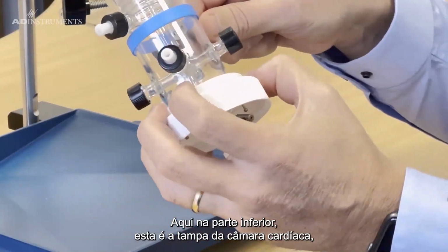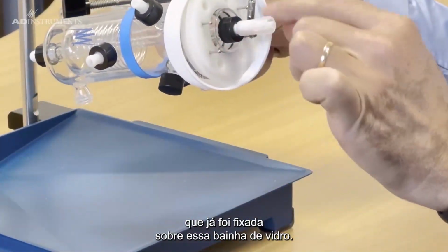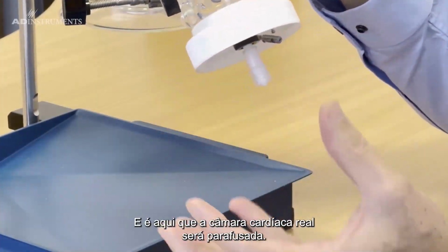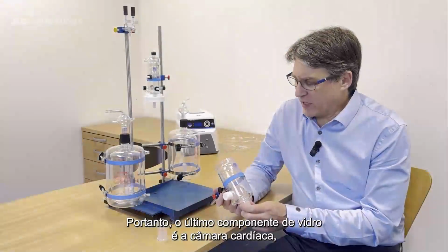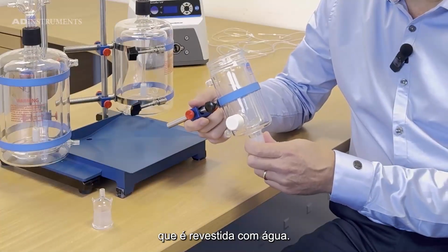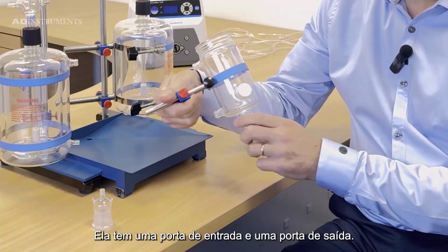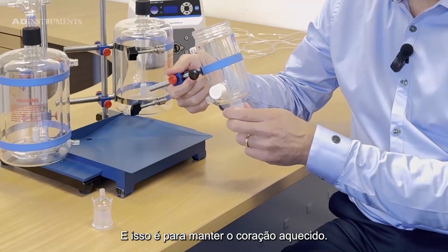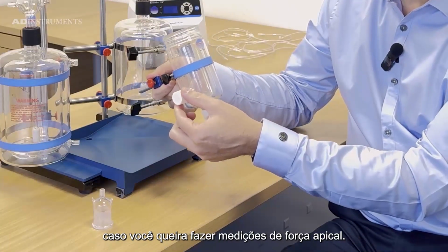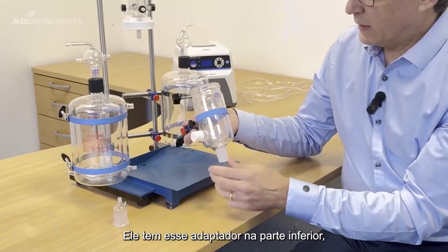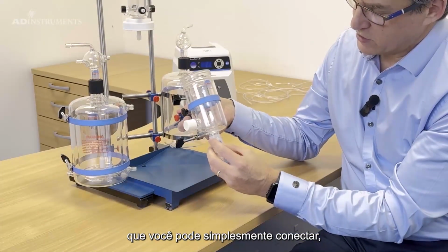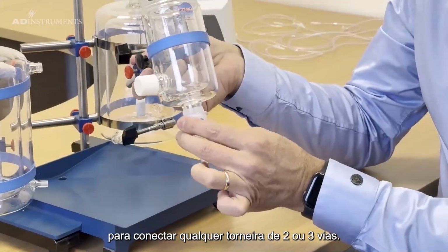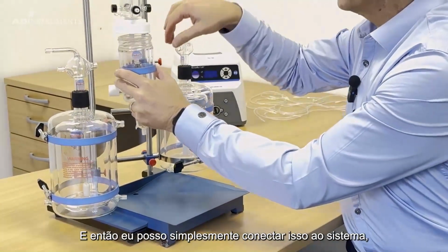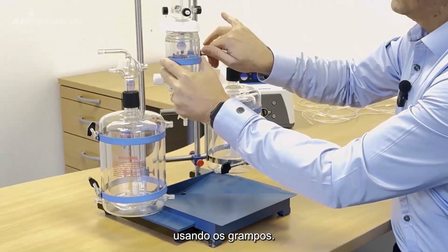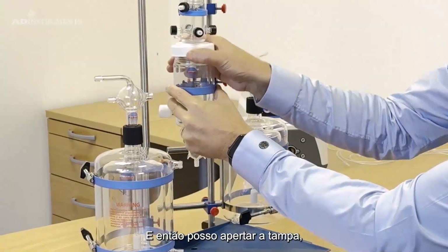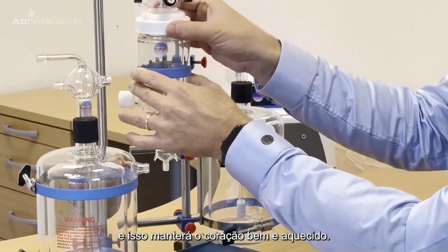At the bottom here, this is the lid for the heart chamber, which has already been attached over this glass sheath. And this is where the actual heart chamber will screw into. So the last glassware component is the heart chamber, which is water jacketed. It has an input and an output port, and this is to keep the heart warm. It also has a port for a pulley system in case you want to do apical force measurements. It has this adapter at the bottom which you can attach to connect any 2-way or 3-way taps. And then I can just attach this to the system using the clamps. And then I can tighten the lid around, and this will keep the heart nice and warm.